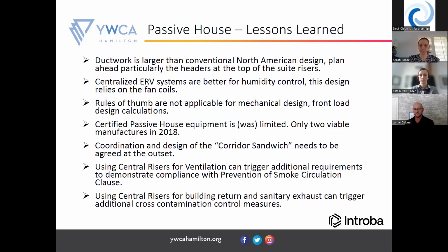We also have a note here about the corridor sandwich - that's really how the services go inside the corridors of each floor of the building. We want to keep the floor to floor low, and that's a constraint, but at the same time there's lighting, refrigerant piping, control boxes that had to go into the ceilings of the corridor, and also ductwork. So we started to run out of room, and if we'd done a better job of setting that up with the entire team earlier in the project, I think we would have had less strife near the tender phase.